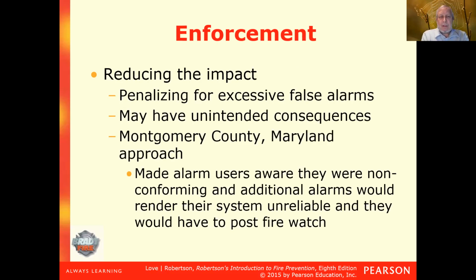To reduce the impact, some jurisdictions penalize excessive false alarms, but may have unintended consequences. For instance, in the Montgomery County, Maryland approach, they made alarm users aware they were non-conforming but didn't fine them, saying additional alarms would render their system unreliable and require a posted fire watch. The unintended consequence is that if you threaten to financially penalize a company for more false alarms, they're liable to just turn off their system, and you don't want that to happen.